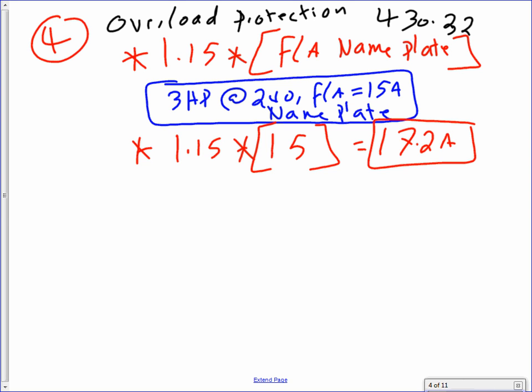There are two types of overloads. One type is a heater, literally a heating element. It heats up and kicks a contact to open. The other type, guys, is electronic. It senses electronically that the current is higher than it's rated for, and it kicks a contact to open. The job of an overload is to interrupt the flow of energy to the motor. So when you set your overload, you're going to set it at 17.2. Cool? 17.2. We don't go up. If it's not 17.2, you have to go down. If you can't set it, you adjust it at 17. There's no 17.2, you have to go to 17. For me, leave it at 17.2 here for the example.